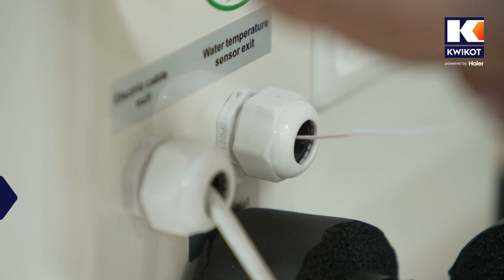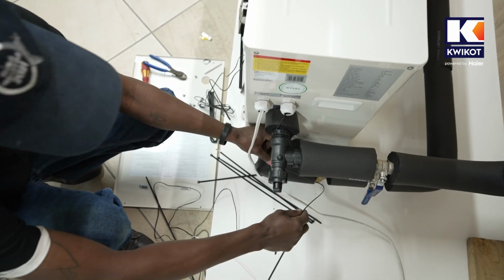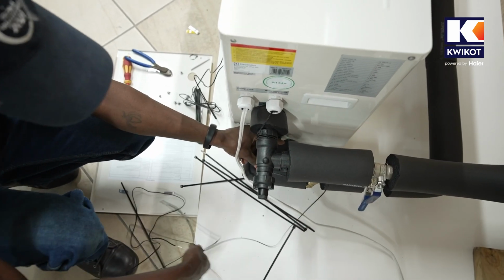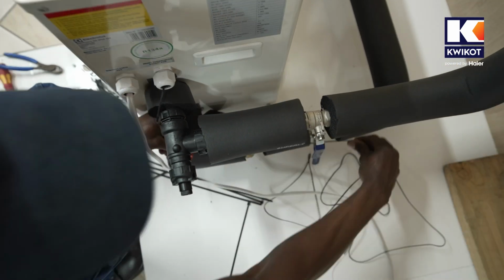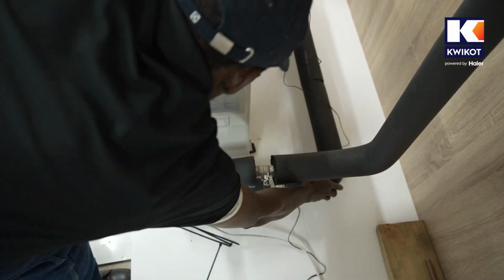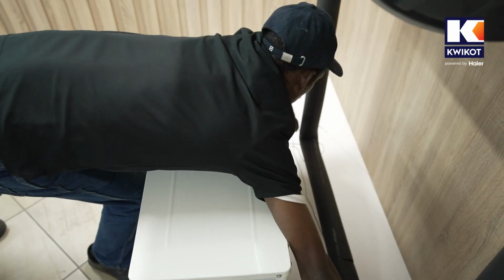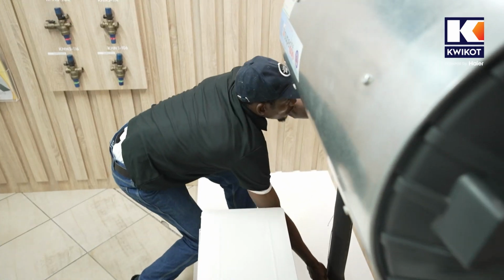And we're now going to install the other end of the microsensor at the thermostat on the water heater. First we're pulling out the microsensor, and then we're going to measure out enough cable to reach the thermostat above, and any excess cable can simply be placed back into the machine and tied down.